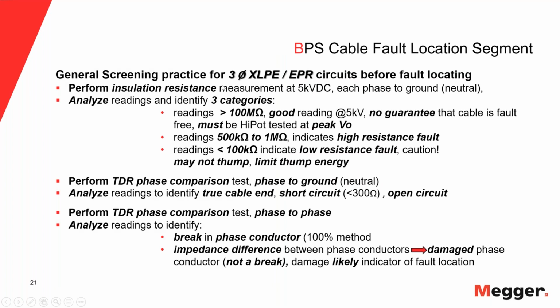When we do fault locating, it's always good not to just go out and hook the thumper up and pray for the best. It's good to do some screening. So what can we do in terms of screening to learn more about the type of fault we have? Because in the end, the type of fault determines what fault locating method will work best to find that fault and to find it in the quickest possible way.